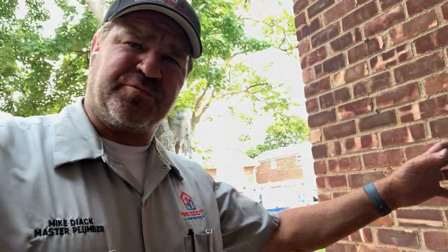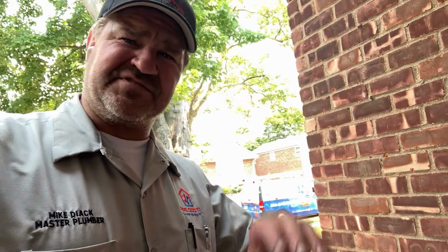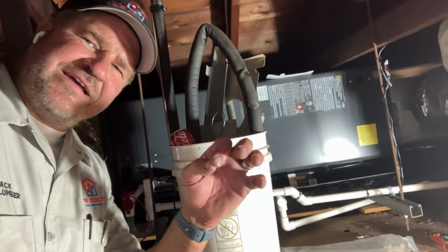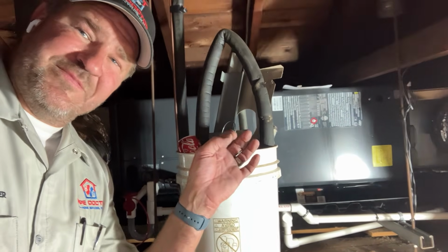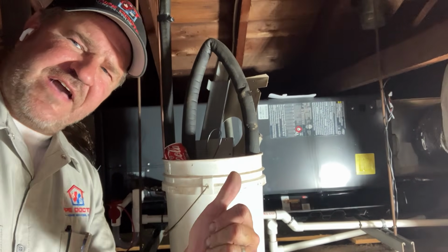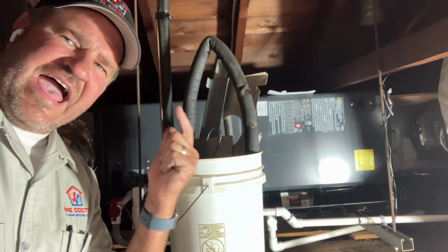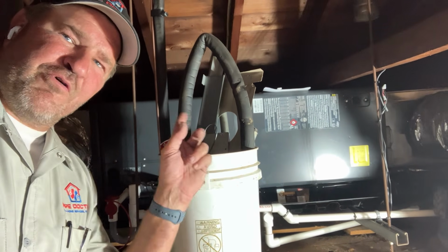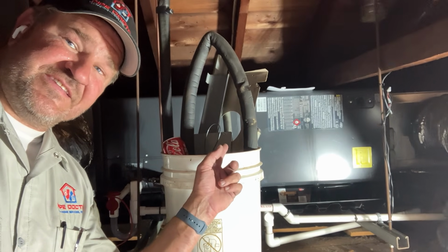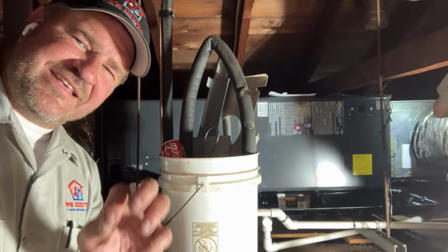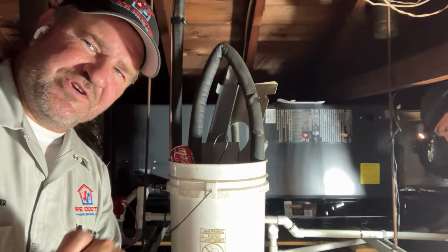And finally, let's talk about reliability, because compressors don't like starting. Every hard start creates heat, electrical stress, and mechanical wear. Since an inverter compressor ramps up gradually instead of slamming on at full speed every cycle, there's less stress on the system throughout its life. So folks, when you combine premium equipment with a meticulous installation, a deep vacuum, proper airflow, accurate refrigerant charge, our lifetime warranty with annual maintenance, we've given this family a system that's built to perform for years to come.